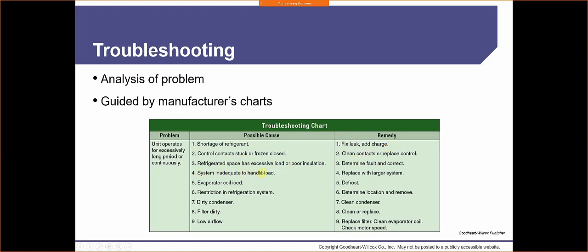System inadequate to handle load. Replace with a larger system. What that means is that somebody came in there and they didn't put in the right size system. It's not cooling or it's not heating the space, and we have an issue. And so part of being a good technician is identifying these problems and really sharing that information with the customer and letting the customer decide on how they want to handle and fix the issue.